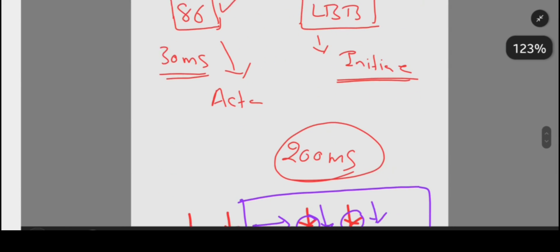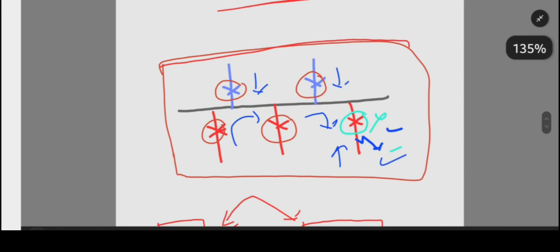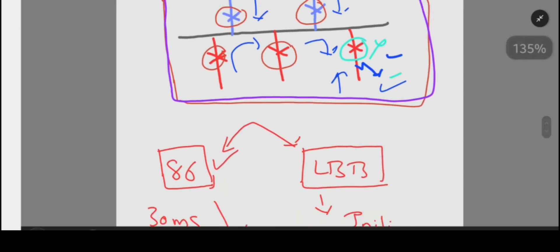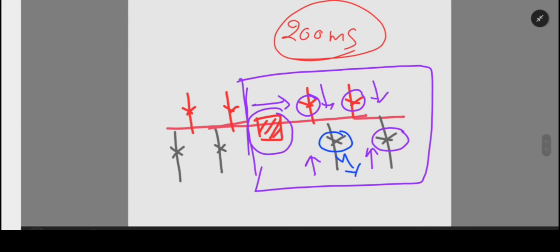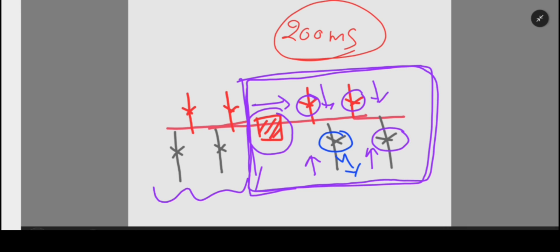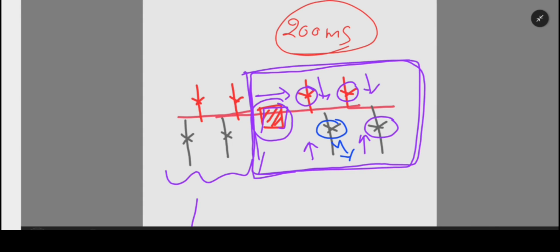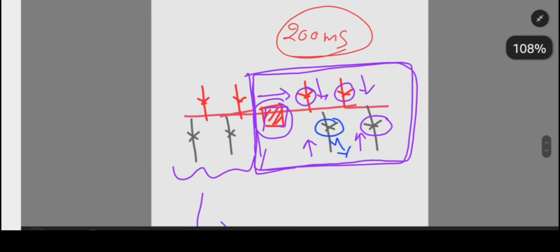What is the difference between the first case and the second case? In the single bus system, the full bus zone goes to shutdown. But in the sectionalized bus system, only zone 1 will go to shutdown and the other zone will be protected. I hope you understand what is the purpose of LBB. LBB is used to provide system stability and comes into the picture when the breaker associated with the fault fails to trip. LBB waits for the master lockout relay trip time of 200 milliseconds. If you have any questions, you can ask in the comment section.